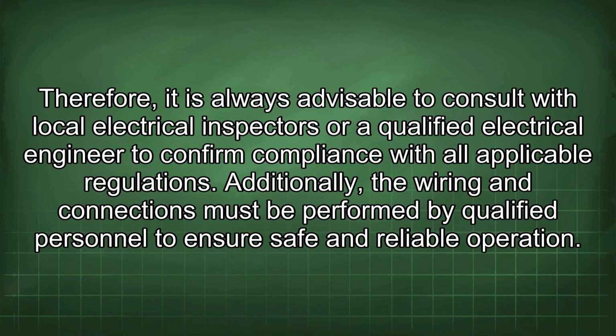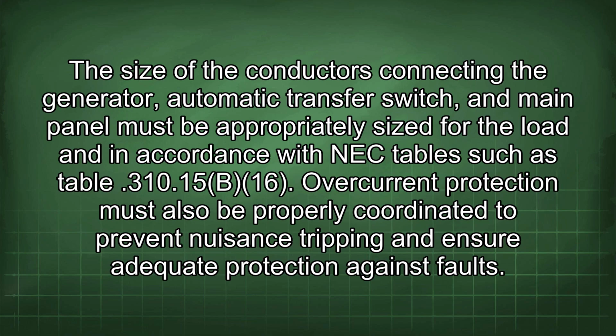Therefore, it is always advisable to consult with local electrical inspectors or a qualified electrical engineer to confirm compliance with all applicable regulations. Additionally, the wiring and connections must be performed by qualified personnel to ensure safe and reliable operation. The size of the conductors connecting the generator, automatic transfer switch, and main panel must be appropriately sized for the load and in accordance with NEC tables such as Table 310.15(B)(16). Overcurrent protection must also be properly coordinated to prevent nuisance tripping and ensure adequate protection against faults.